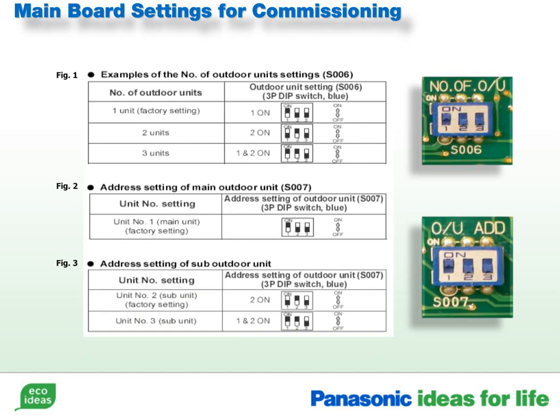Now we have to set the number of outdoor units, and outdoor unit address. Figure number 1 shows the possible configurations available when combining 2 or 3 units. By default the factory sets the condenser to be a standalone unit. If you are combining 2 outdoor units for increased capacity, you will have to set the board on the main unit to recognize 2 condensers.